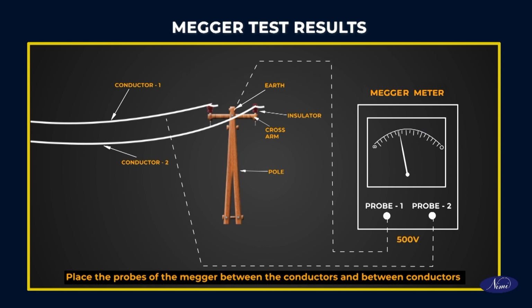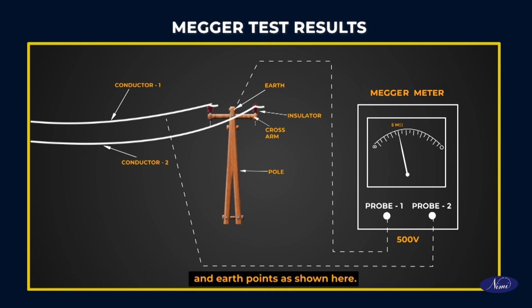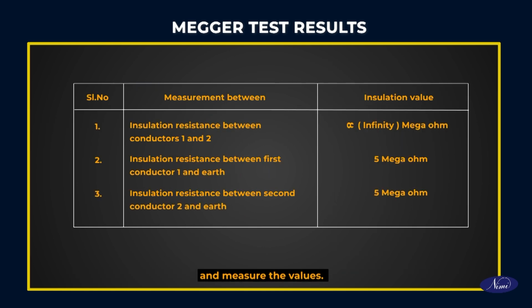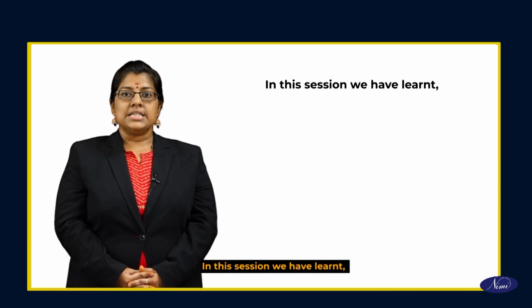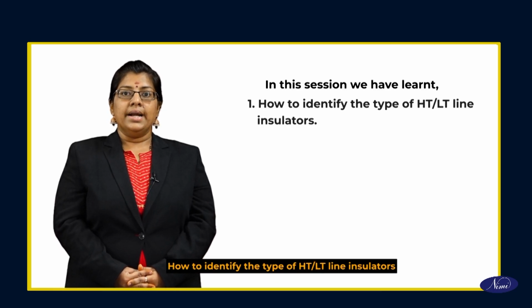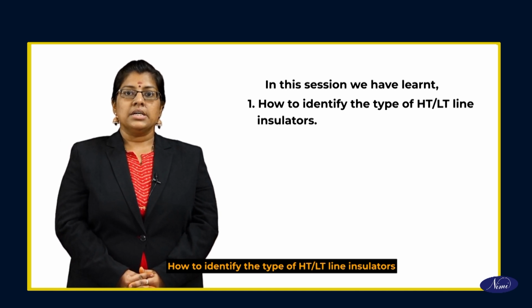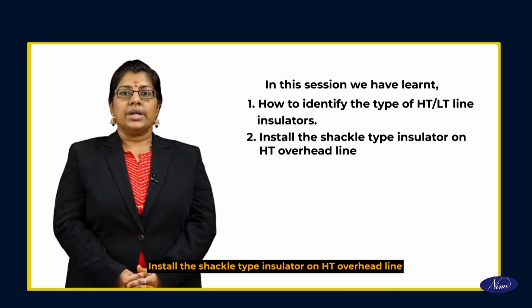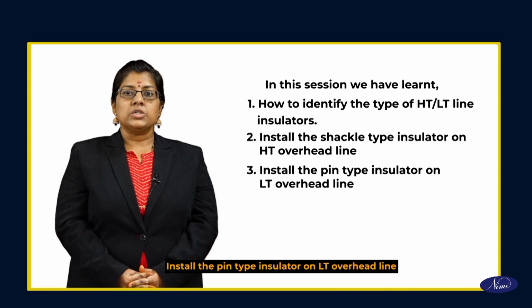Place the probes of the Megger between the conductors and between conductors and earth points as shown here, and measure the values. Record the values in the table. Recap. In this session, we have learnt how to identify the type of HT, LT line insulators. Install the shackle type insulator on HT overhead line. Install the pin type insulator on LT overhead line.